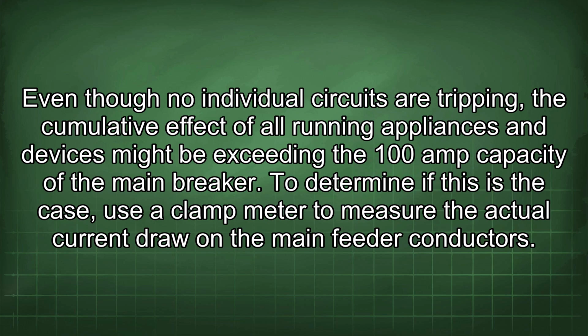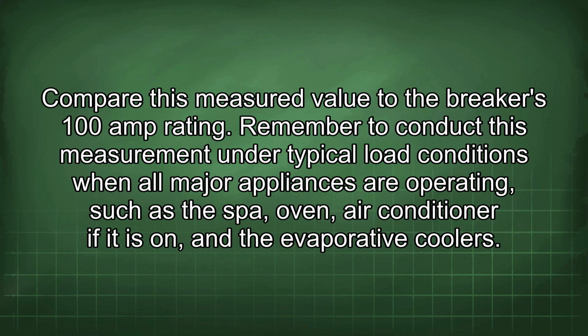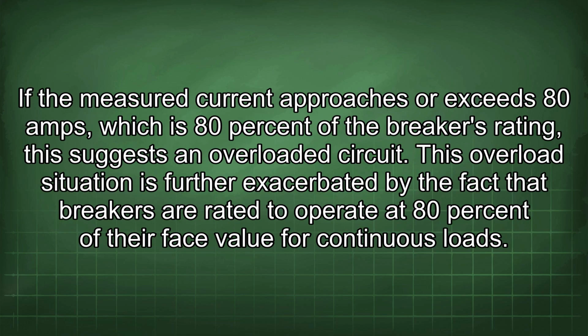To determine if this is the case, use a clamp meter to measure the actual current draw on the main feeder conductors. Compare this measured value to the breaker's 100 amp rating. Remember to conduct this measurement under typical load conditions when all major appliances are operating, such as the spa, oven, air conditioner if it is on, and the evaporative coolers. If the measured current approaches or exceeds 80 amps, which is 80% of the breaker's rating, this suggests an overloaded circuit. This overload situation is further exacerbated by the fact that breakers are rated to operate at 80% of their face value for continuous loads.